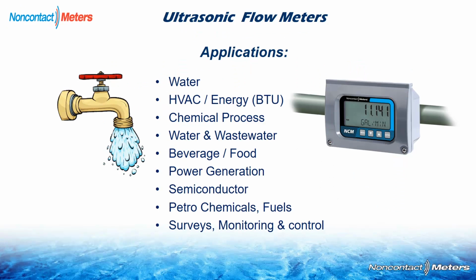Here are a few typical applications, and yes, the majority of them will be water. But water is used in many different aspects of monitoring, such as inventory and process control. And here are some typical applications like HVAC. Energy applications are very popular for, say, chilled water, hot water, boiler feed. Chemical processes, so again, you can see it doesn't actually have to be water, but it's a liquid application. So as long as you don't have a massive amount of suspended solids or aeration, it's typically a good application for a transit time flow meter to work on.